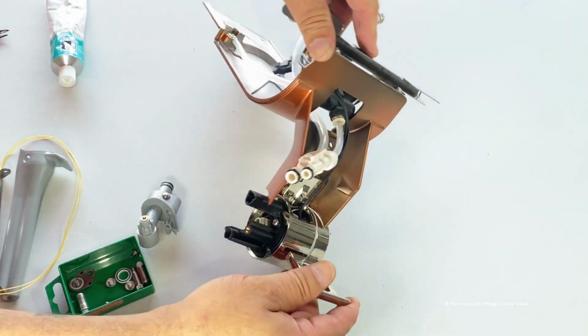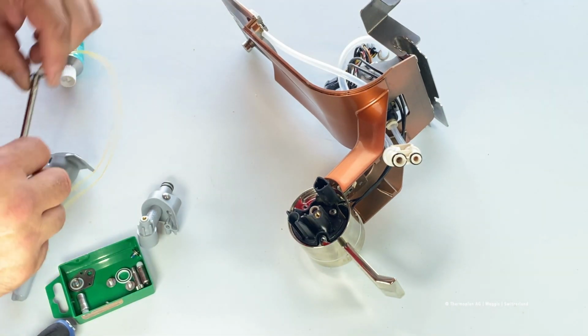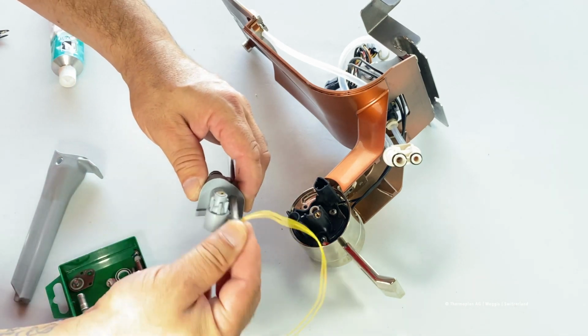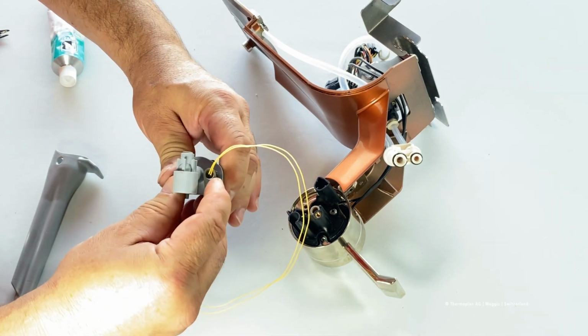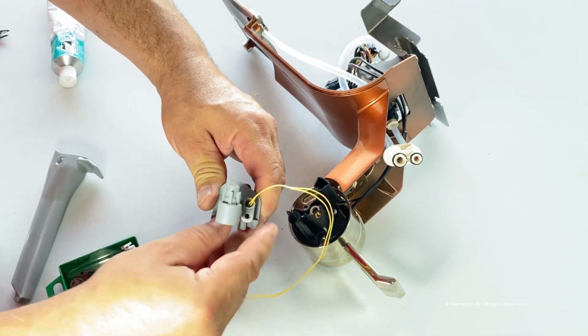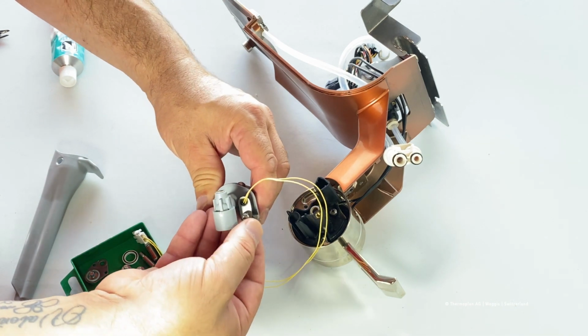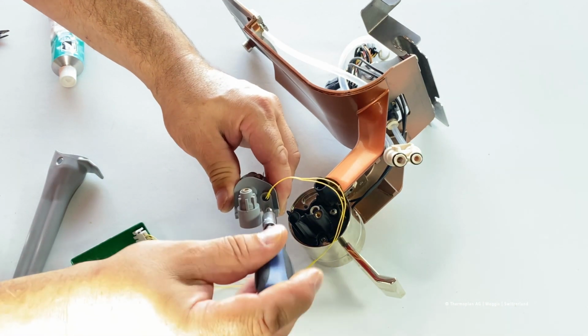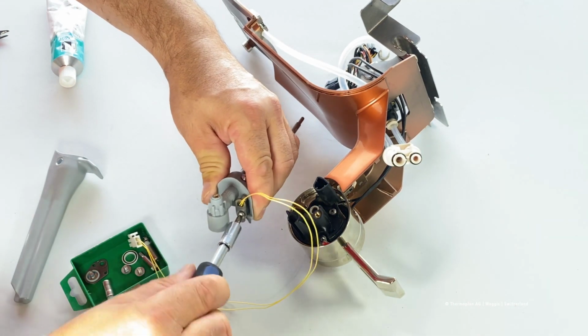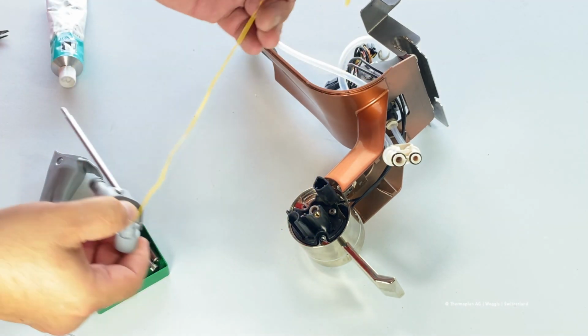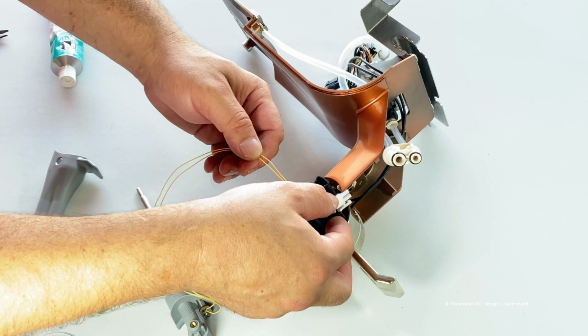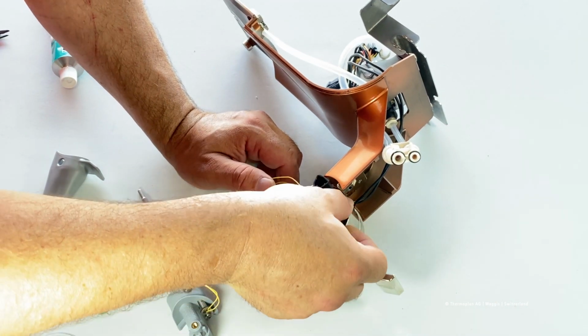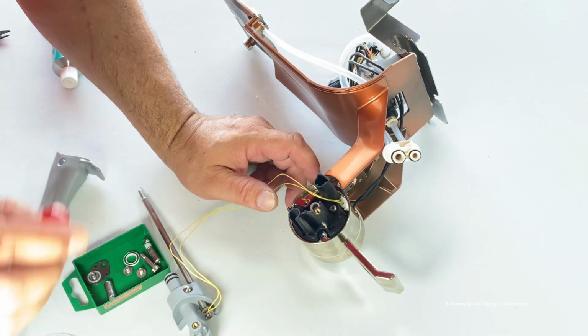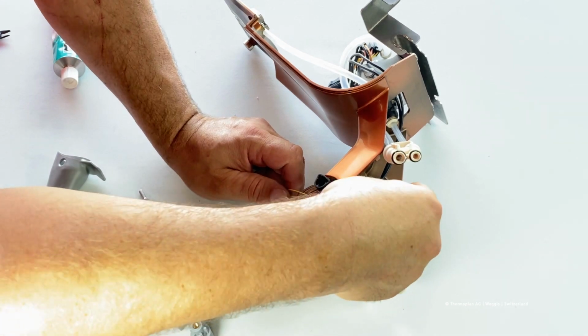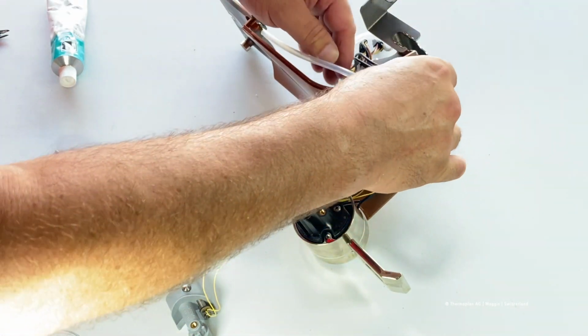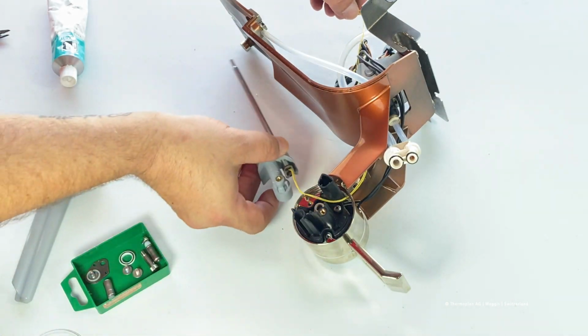Next, I'm going to mount back the NTC probe to the steam connection piece and put the plastic screw back on. Also, don't tighten this one too much. The plastic can easily break. Then I route the NTC wire through the housing. Sometimes it helps with a little tool. In my case, I took a little screwdriver and routed it through the housing of the actuator.